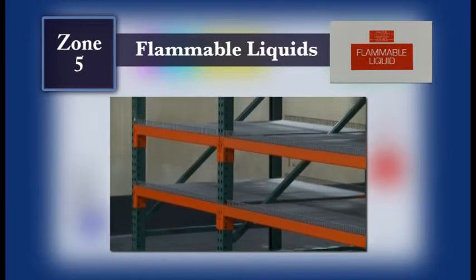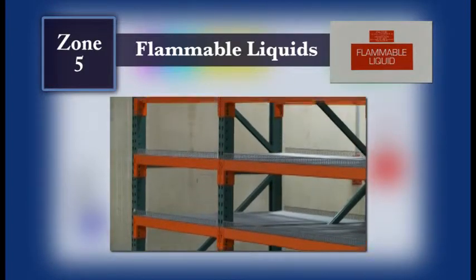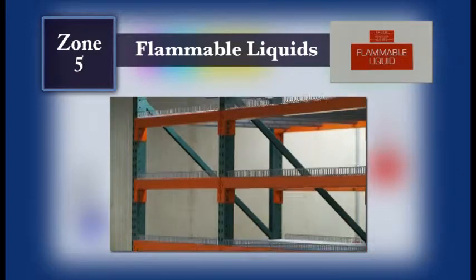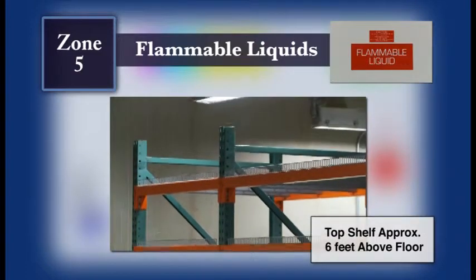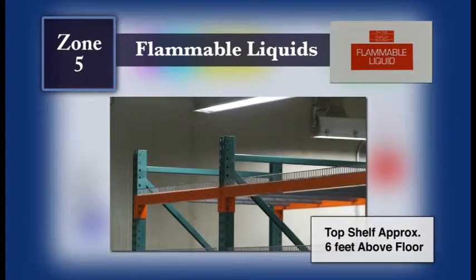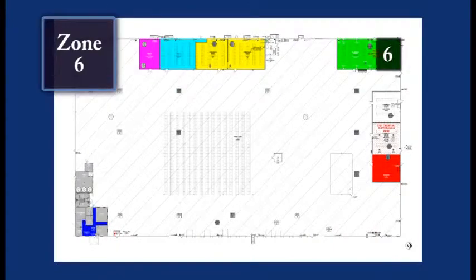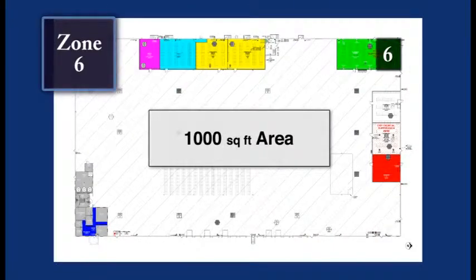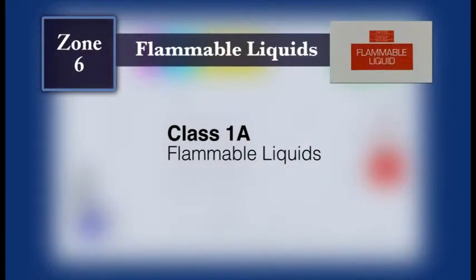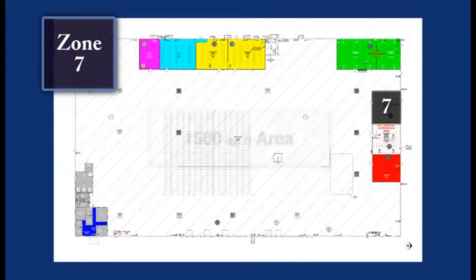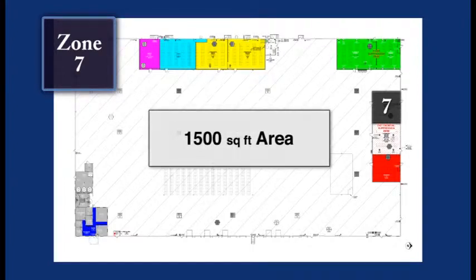Product is arranged in a wire rack system. The racks are installed to create a space between each rack. Rack height is up to a maximum of 6 feet above the concrete floor. Zone 6 is a 1,000 square foot area adjacent to the flammable liquids room and designated for Class 1A flammable liquids. Zone 7 is an area approximately 1,500 square feet in size housing flammable solids.